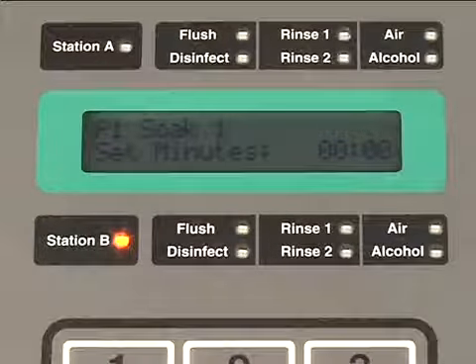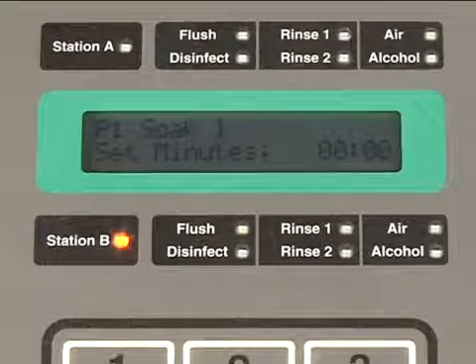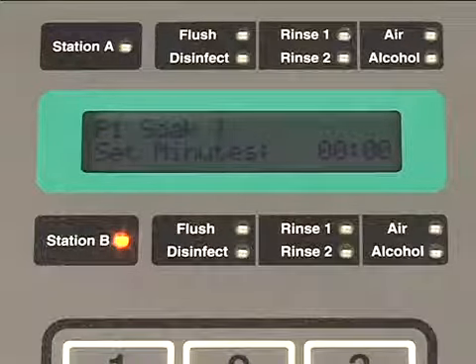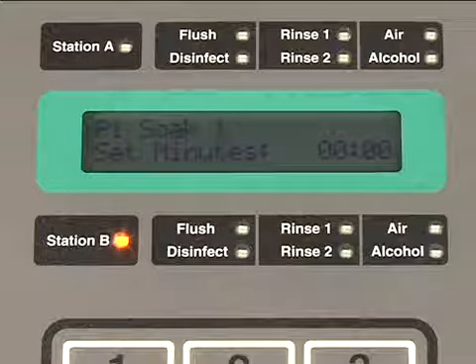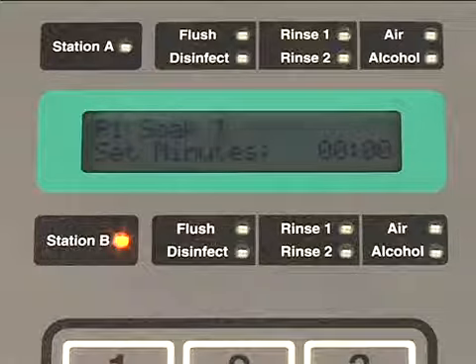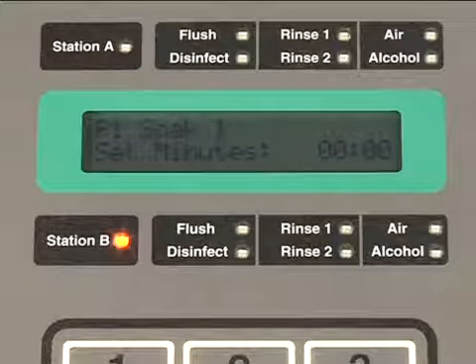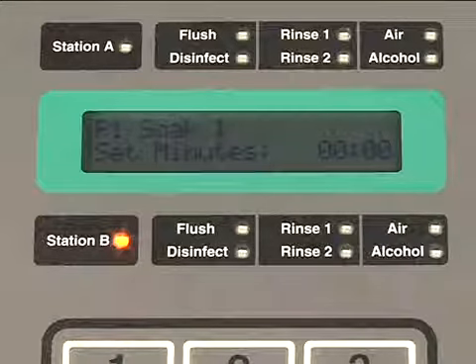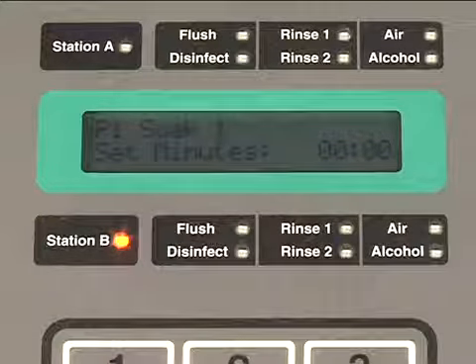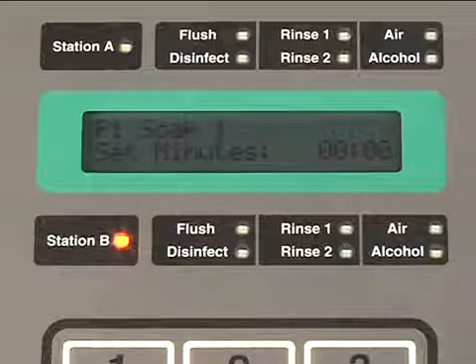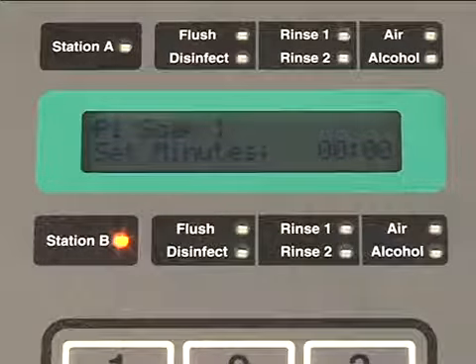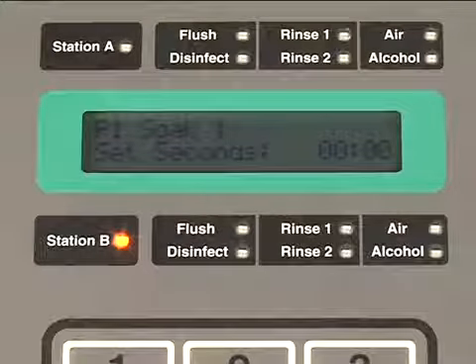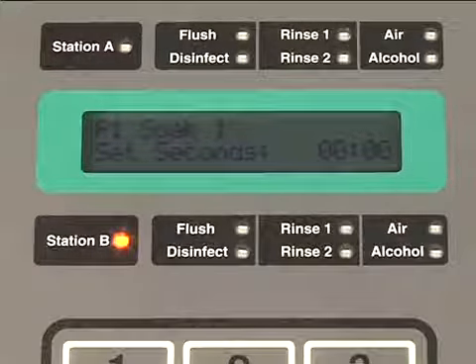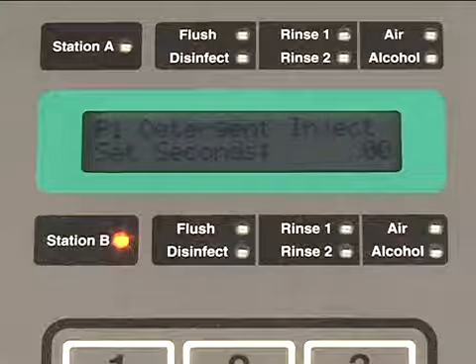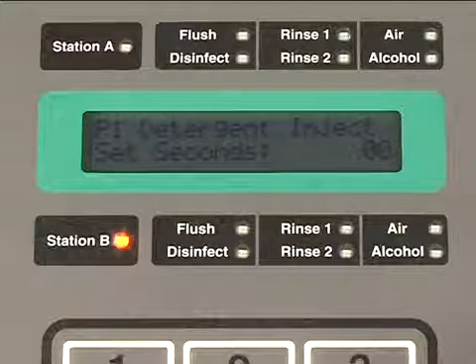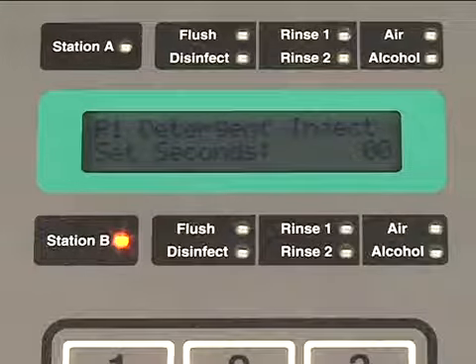The next prompt is to set the detergent soak time. When following the SGNA standards and manufacturer cleaning guidelines, you may choose to skip both the detergent soak and the detergent inject functions. These steps should have already been performed when the endoscope was manually pre-cleaned. To skip these functions, enter 0 for each of the values. Therefore, for the detergent soak minutes and seconds, we will enter a 0 followed by Enter. And for the detergent inject prompt, we will enter a 0 for the seconds. Each second corresponds to approximately 3 cc's of detergent. Different detergents have different dilution levels.